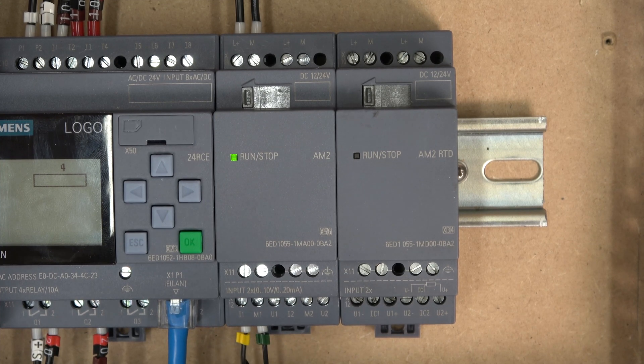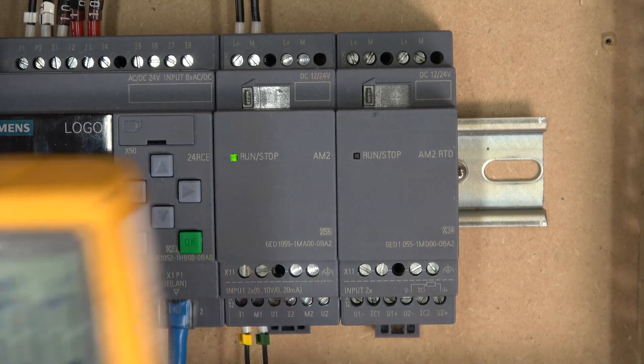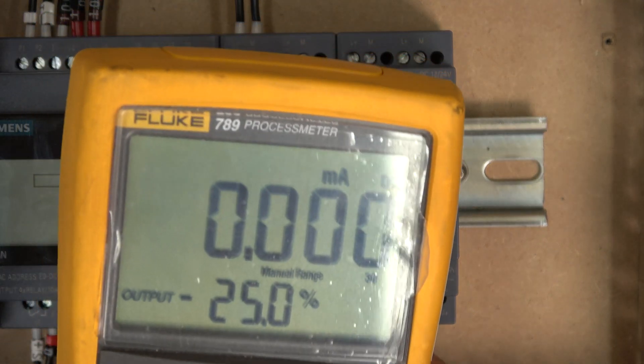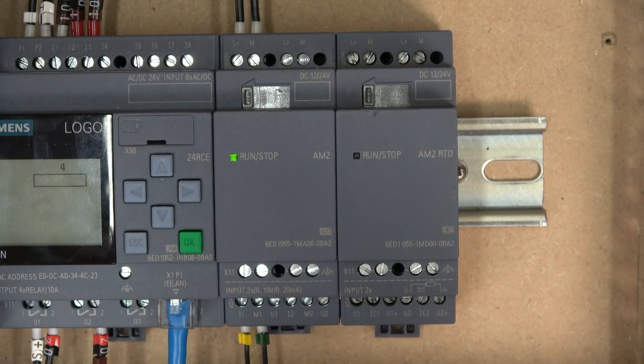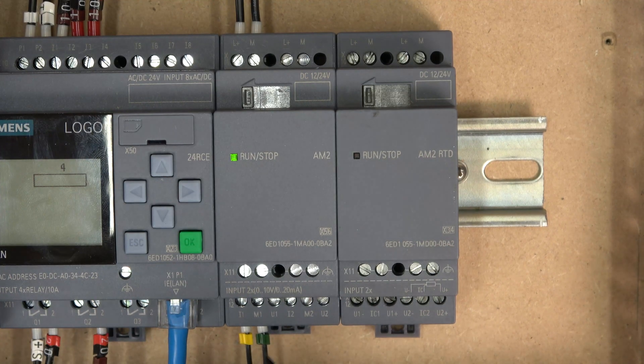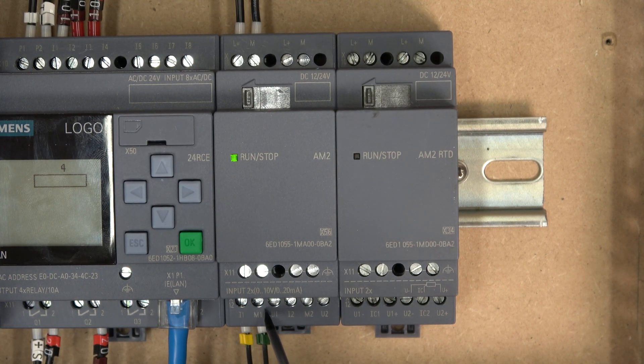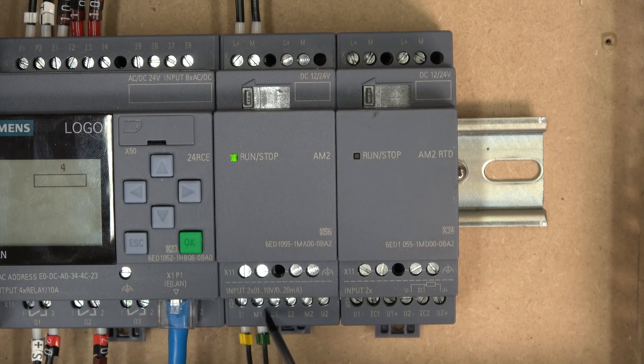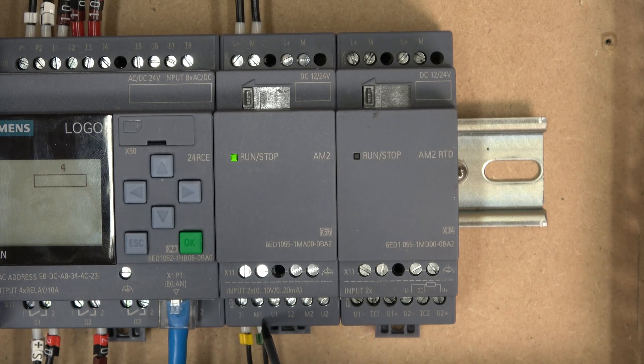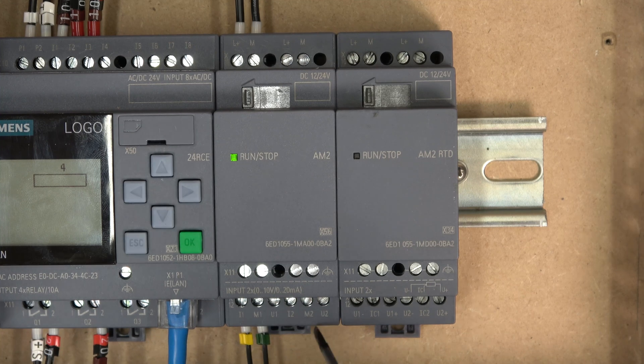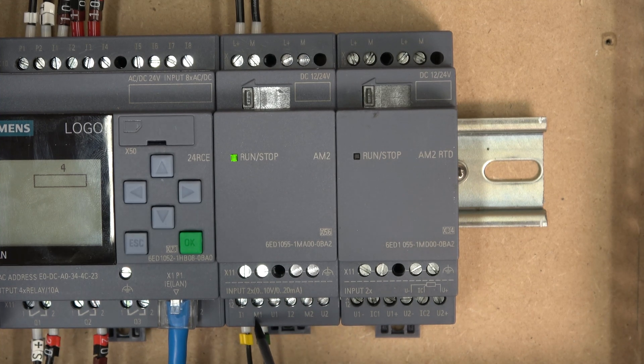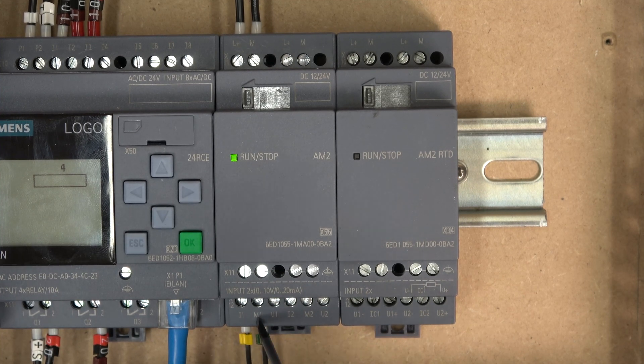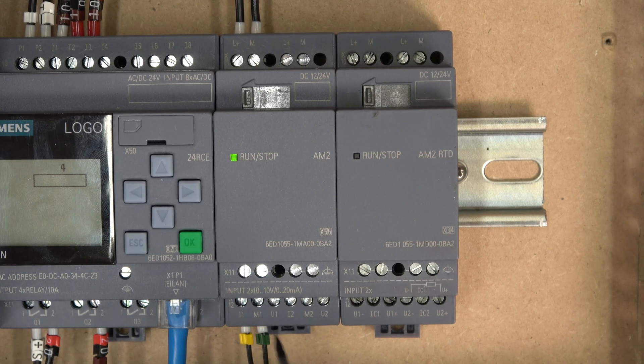Because I'm going to be using this guy here, Fluke process meter, to generate our 4 to 20 milliamps. So your sensors are going to be outputting the plus and the minus, so basically this M1 is always going to stand for the minus. If you're doing voltage, minus will come in here. If you're doing current, minus will come in here. That's basically what the M stands for.